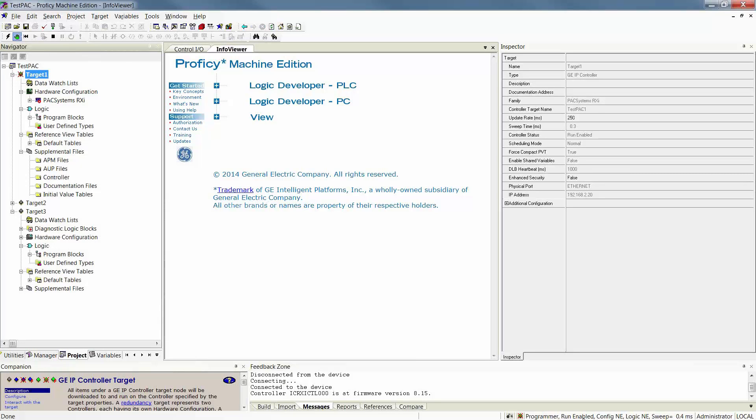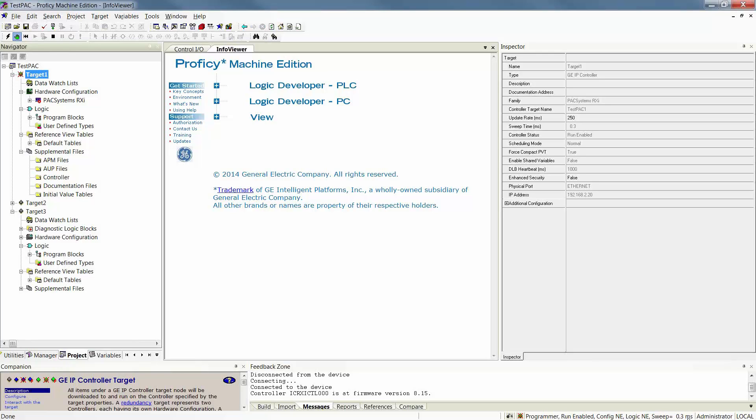You'll notice then that it references Programmer Mode. You'll also notice that when I'm online, it will tell me whether or not my controller is running or it's stopped. You'll also notice that you have a red X indication if you are either not equal on your configuration or not equal with your logic. Your sweep or your scan time will also show next to this.